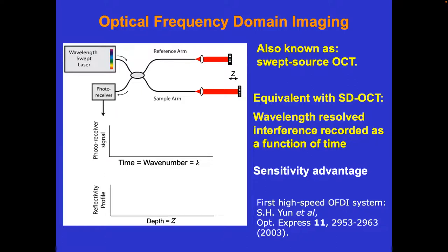And what you measure now at the photo receiver is a signal that is a function of time. But since the laser is sweeping its wavelength, it's actually a function of wave vector k. And then you have the same amount of information that you do with the spectrometer: you have your intensity as a function of wave number, you do your transform, and so you get your depth information.